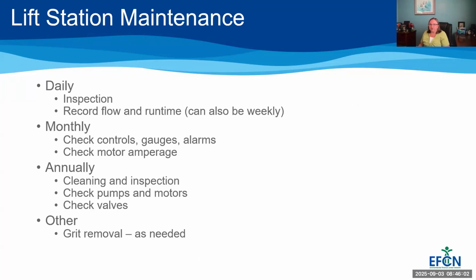So when we're thinking about lift station maintenance, things that we need to do daily, monthly, annually. Daily, of course, we want to inspect them. We want to record the flow and the runtime. If it's a lift station that's not got a high flow rate, that could maybe be moved to weekly instead of daily. Monthly, we want to check our controls, our gauges, our alarms, make sure they're all working the way that we expect them to. We might want to check our motor amperage and make sure that the motor on the pump is what we think it should be. It's not showing any wear and tear. Annually, we want to clean and inspect. We want to check the pumps and the motors. We want to check that the valves are operational. And then grit removal is kind of on an as-needed basis.